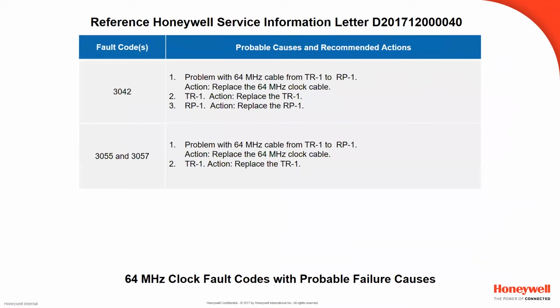We saw previously that only if a 3055 is logged, then the TR is faulty, and only if a 3057 is logged, then RP is faulty. There is a possibility for both of these fault codes occurring together, which clearly indicates a 64 megahertz cable connectivity issue. And the first action would be to inspect, and if required, replace the 64 megahertz clock cable.